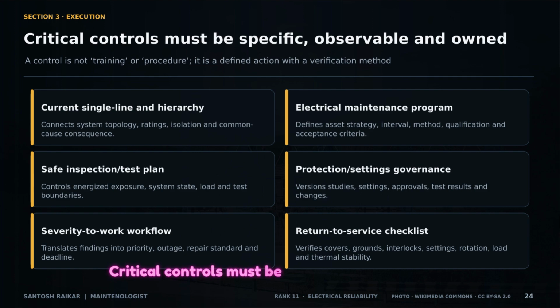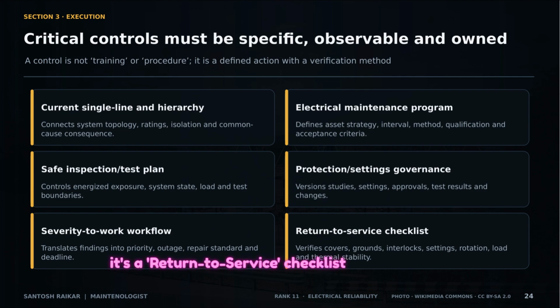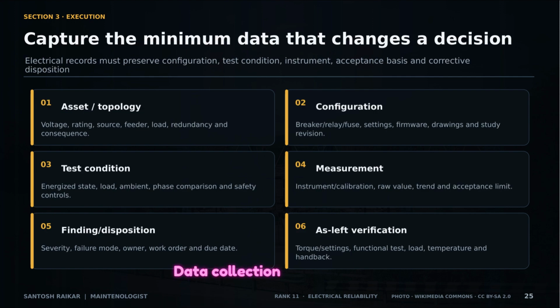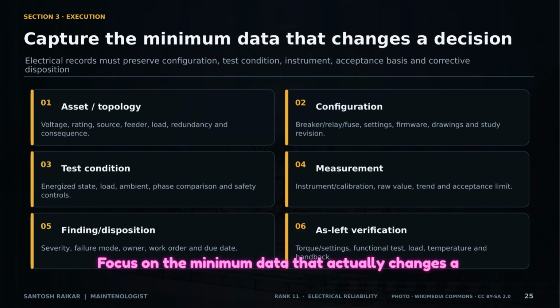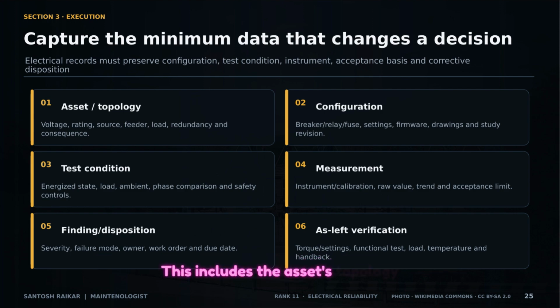Critical controls must be specific and observable. A control isn't just a manual on a shelf. It's a return to service checklist that someone physically ticks off, or a severity to work workflow that automatically triggers a repair based on a thermal finding. Data collection should be lean. Focus on the minimum data that actually changes a decision. This includes the asset's topology, the test conditions like ambient temperature, raw measurements, and the as-left verification details.